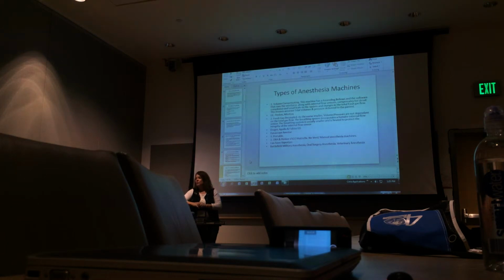One of the distinguishing things about the fresh gas decoupled system is that their breathing system will be heated, and that will be to protect the flow sensor. It has nothing to do with clinical applications to the patient. It's purely and simply to protect a hot wire flow sensor. In the Draeger, it's a little Venturi unit with crosshairs in it, and these two wires are heated. It can tell by the flow going over it, the change in the temperature and the change in the resistance, what the tidal volume actually is. It's highly sensitive, highly sensitive.